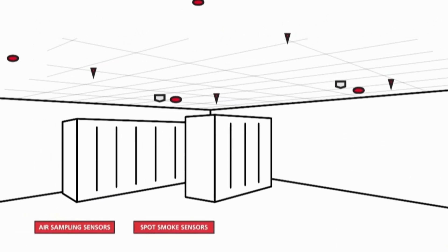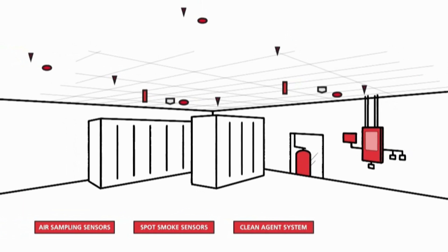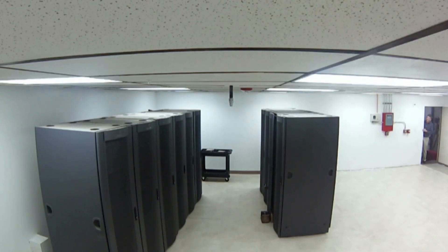The room is equipped with VESDA air sampling and spot smoke sensors, plus the clean agent fire suppression system and nine water sprinklers. When everything is ready, the clean agent test is run first.